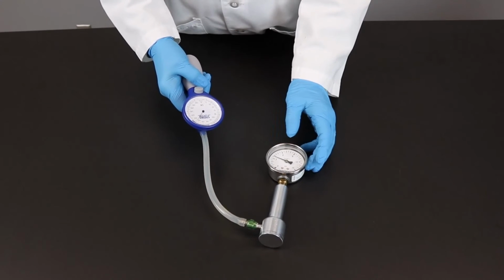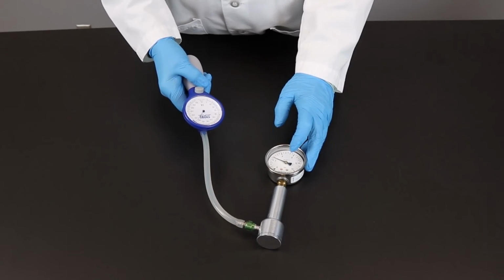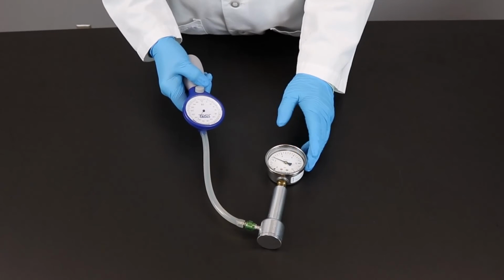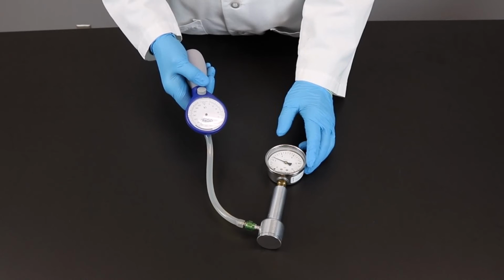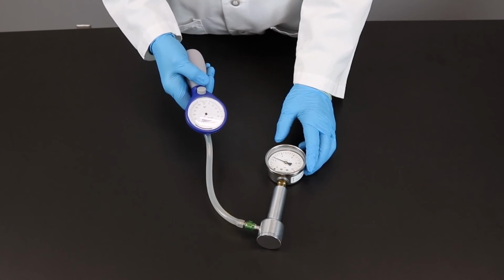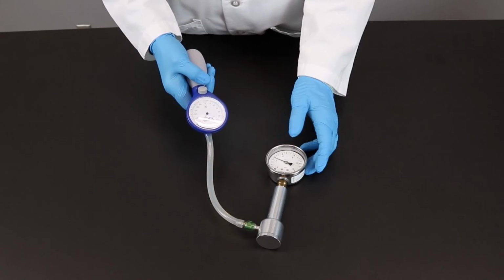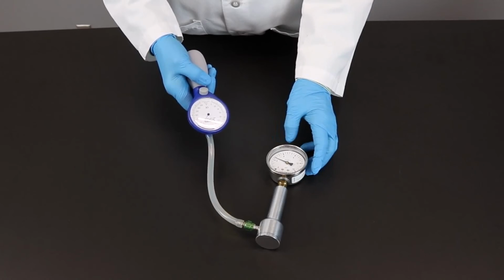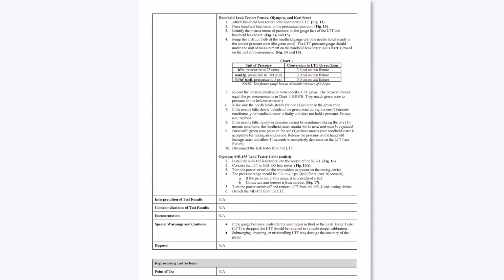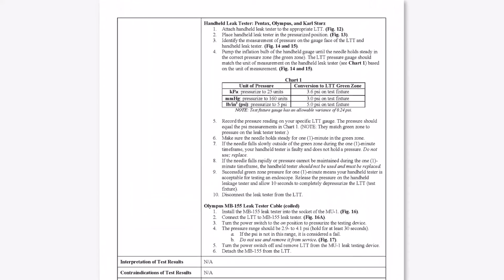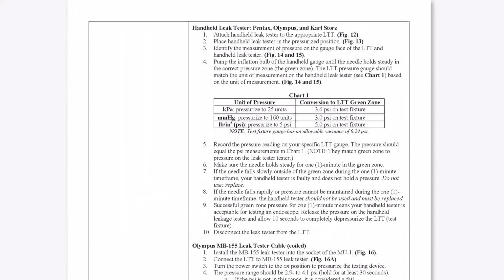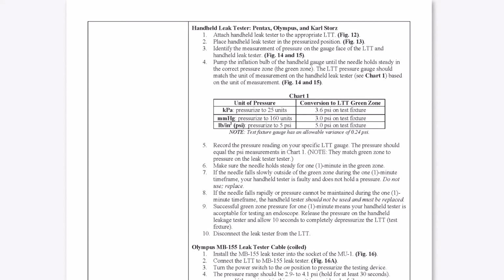The other thing we want to point out is that our gauge measures in psi. This handheld leak tester measures in millimeters of mercury. You want to make sure that the values equal each other, and the way to do that is to reference our conversion table in our IFU, where we convert psi to millimeters of mercury.